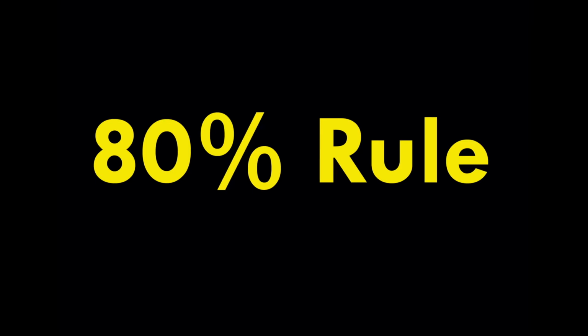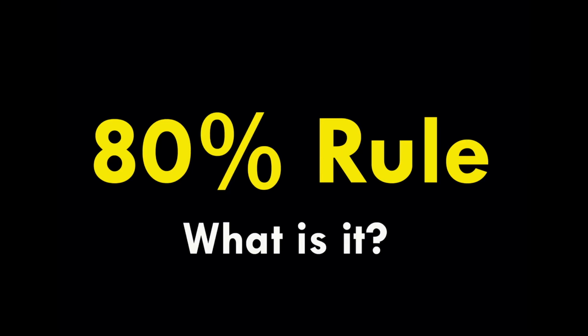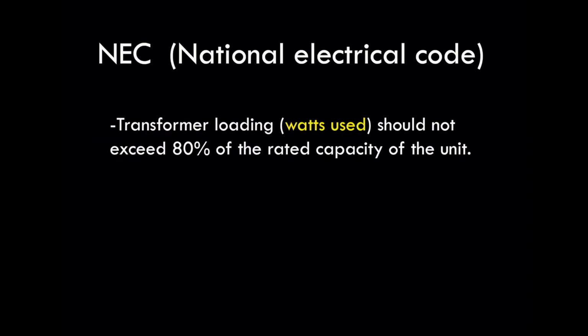Before we get into covering how to size a transformer that's right for your project, we first need to cover the 80% rule. Now the 80% rule is a rule we use in landscape lighting to dictate the size of the transformer that you're going to need for your project. The National Electrical Code states that transformer loading, which is the watts used, should not exceed 80% of the rated capacity of that unit. In other words, when we add up all the watts of the bulbs and the lights we're using, it should never exceed 80% of the total rated capacity of that transformer.